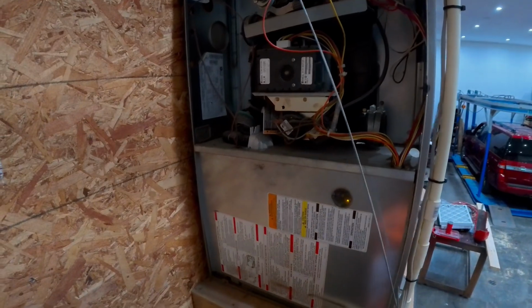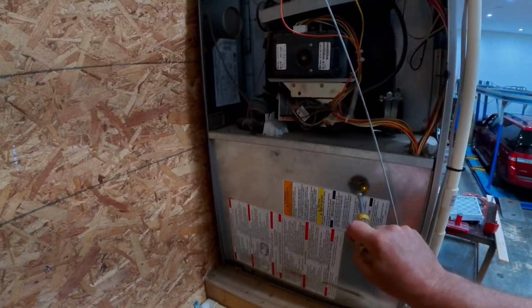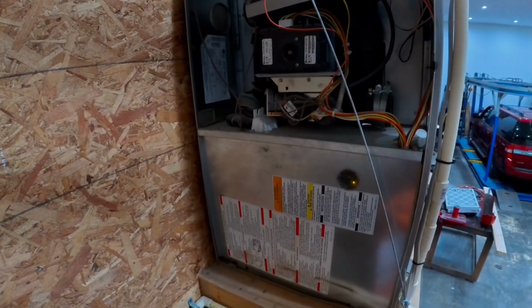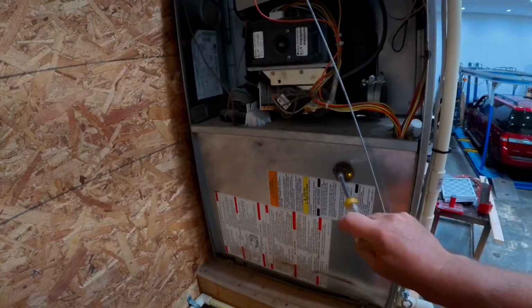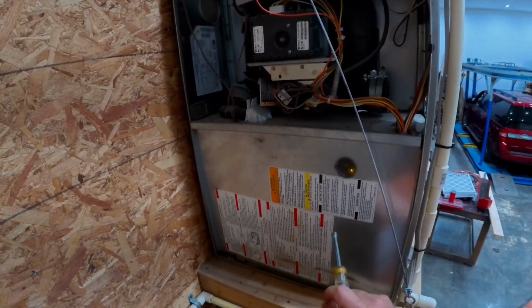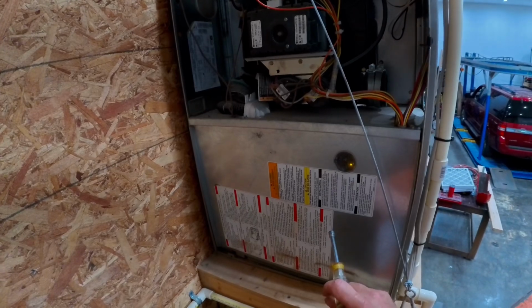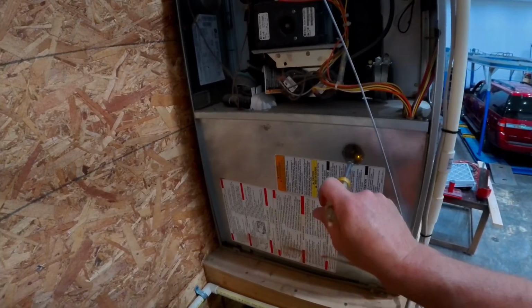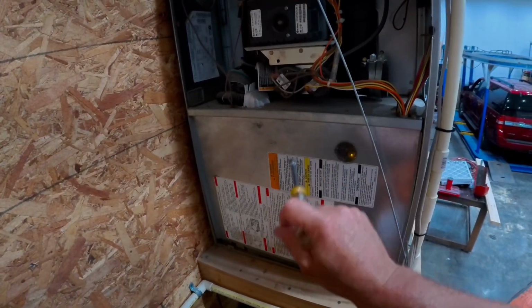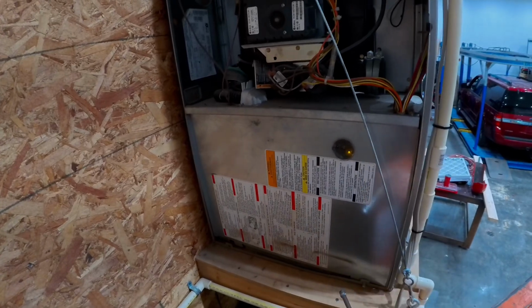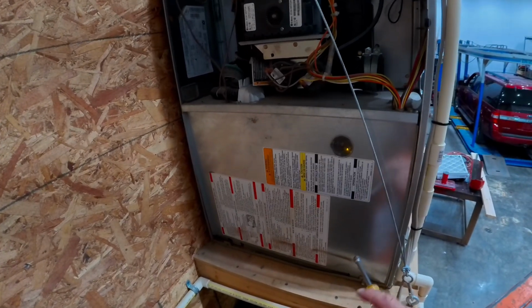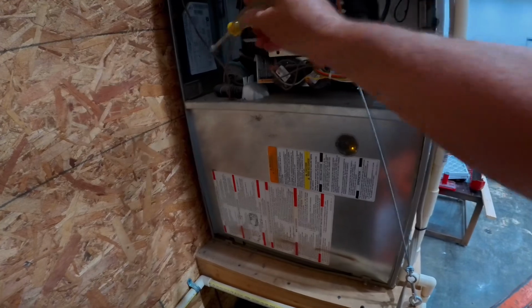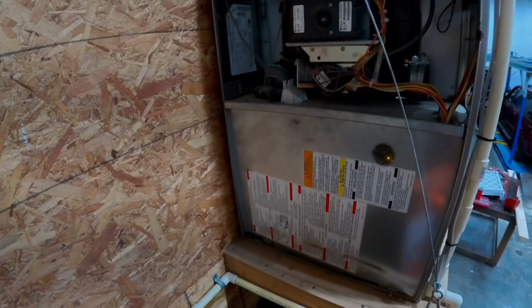But for this scenario, we're going to go with the fact that we have power at the unit, so now what, right? What we're going to do now is remove the service panel, which is going to access the blower compartment. Behind the blower compartment is pretty much a circuit board. That's what that little light is. And that's where all of our thermostat wiring is going to be connected. And that's what we need to get to next. On this unit, there's 2 5/16 screws, one at the top of each corner, and this panel is going to come off.